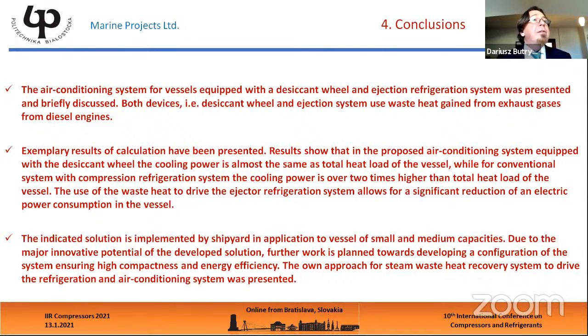If you can decrease condensation temperature, and if you have 12 centigrades evaporation temperature and 90 centigrades, you can have a coefficient of performance as much as 0.5, even 0.45, something like that. It is possible. But the problem is with condensation temperature. If you have condensation temperature 35, 33, I guess it will be possible. If you have 44, it is really very problematic. Probably you can do that, but with COP, which will be significantly lower.